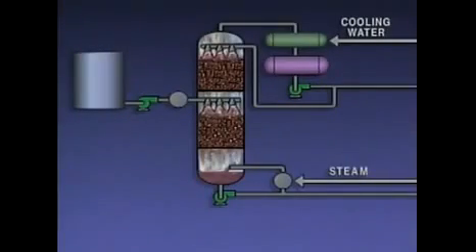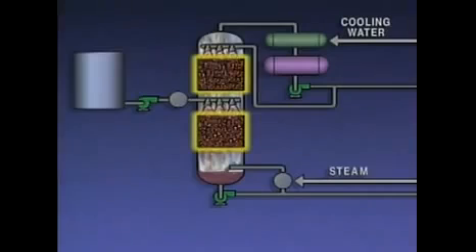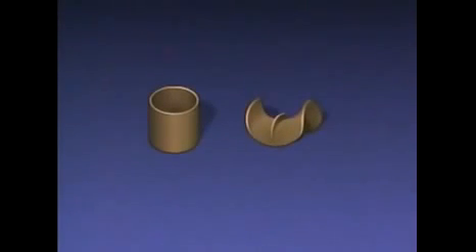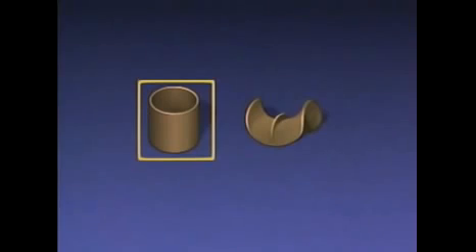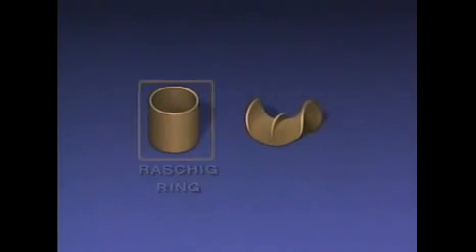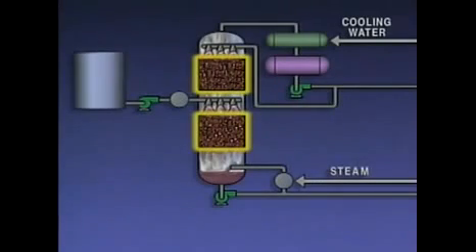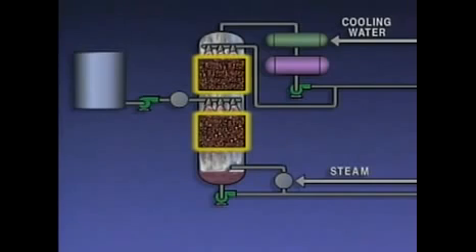Another type of tower, called a packed tower, contains layers of devices called packing instead of trays with bubble caps. There are many different types of packing. Some towers have sections that are filled with cylindrical rings like the one illustrated here, known as a Raschig ring. Another type of packing is known as a Berl saddle. The packing breaks up the liquid so that it flows over a large amount of surface area. This exposes more of the liquid to the vapors and increases heat transfer from the vapors to the liquid.